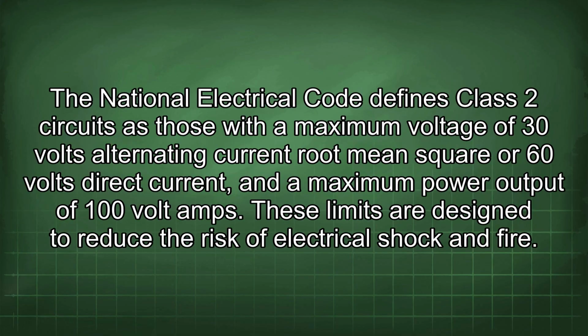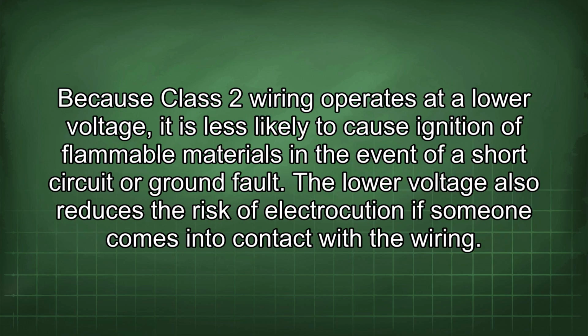The National Electrical Code defines Class 2 circuits as those with a maximum voltage of 30 volts alternating current root mean square or 60 volts direct current, and a maximum power output of 100 volt-amps. These limits are designed to reduce the risk of electrical shock and fire. Because Class 2 wiring operates at a lower voltage, it is less likely to cause ignition of flammable materials in the event of a short circuit or ground fault. The lower voltage also reduces the risk of electrocution if someone comes into contact with the wiring.